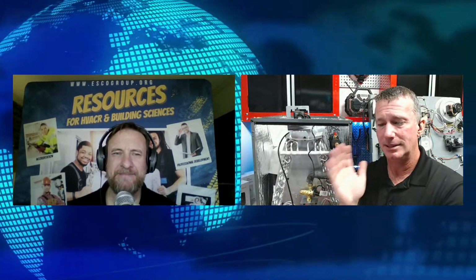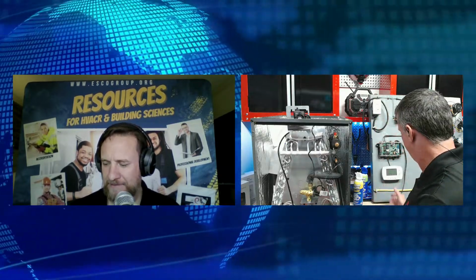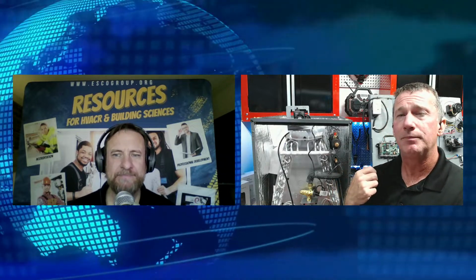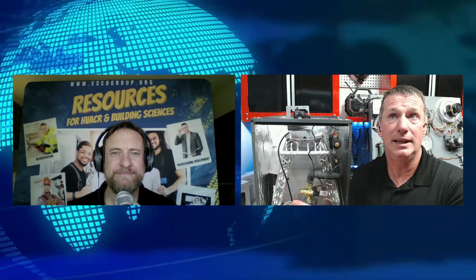So within 5 seconds, I went into a state of soft lockout where I actually turned power off to this thermostat. So I shut off my 24 volts to my thermostat. I turned off my call for heat, and I initiated my blower. This one's not running the draft inducer because we didn't have the combustible gases within the heat exchanger compartment. We only had it in the air stream. Therefore, we just used our blower.